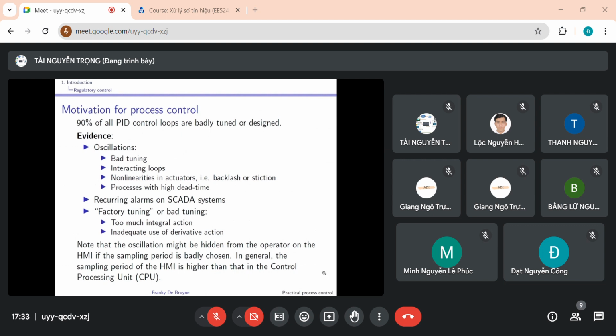Well, there is a lot of evidence for that, and the indicators that are shown here are very important as they allow you to assess the control performance of a production line. Oscillations are certainly a sign of problems with the associated control loop. It can come from bad tuning, so for instance, too much integral action, inadequate use of the derivative action, and so on. Oscillations can also come from interacting loops, so coupling effects, non-linearities in actuators, and a good candidate is stiction. We'll come back to this later in the course, but you have seen that it comes back in these surveys.